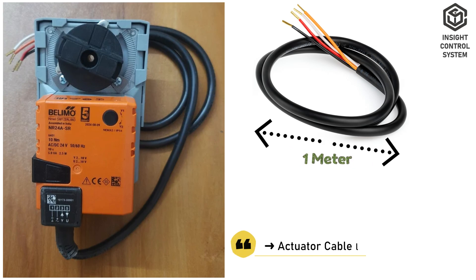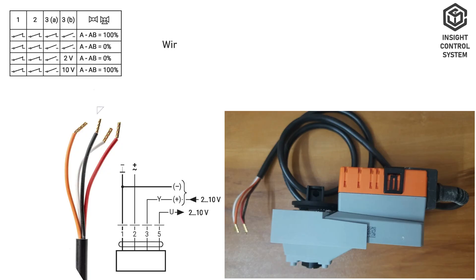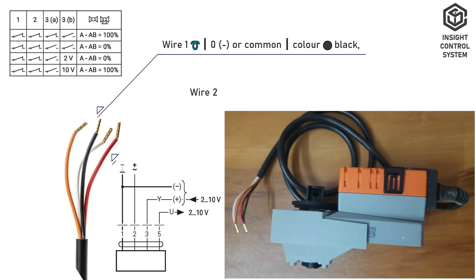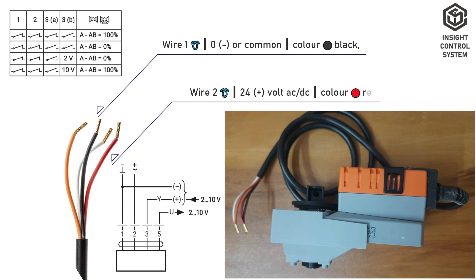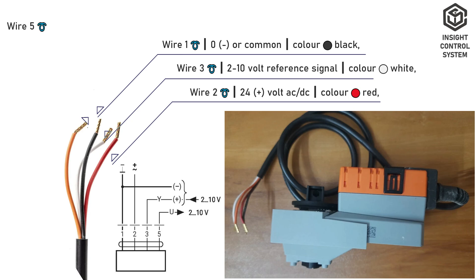Wiring: actuator cable length is 1 m; actuator cable size is 4-core 0.75 mm². Wire 1 is 0V or common, color black. Wire 2 is 24V AC or DC, color red. Wire 3 is 2 to 10V reference signal, color white. Wire 5 is 2 to 10V feedback signal, color orange.